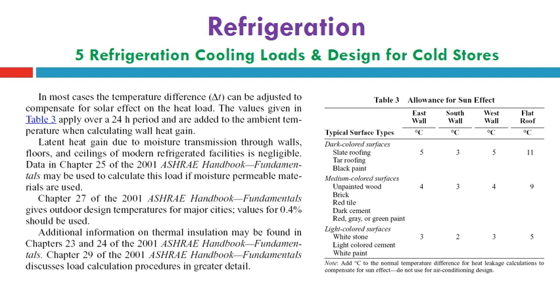The values given in Table 3 apply over a 24-hour period and are added to the ambient temperature when calculating wall heat gain. Latent heat gain due to moisture transmission through walls, floors, and ceilings for modern refrigerated facilities is negligible. Data in Chapter 25 of the 2001 ASHRAE Handbook Fundamentals may be used to calculate this load if moisture permeable materials are used.